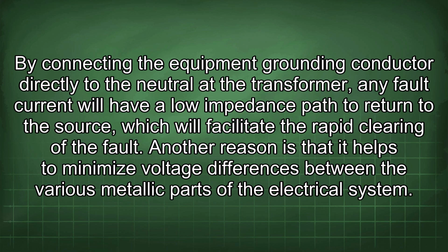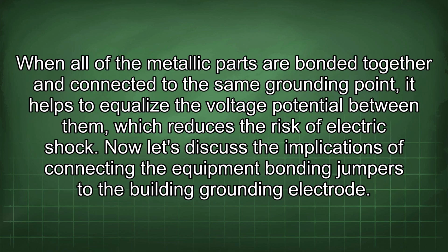Another reason is that it helps to minimize voltage differences between the various metallic parts of the electrical system. When all of the metallic parts are bonded together and connected to the same grounding point, it helps to equalize the voltage potential between them, which reduces the risk of electric shock. Now let's discuss the implications of connecting the equipment bonding jumpers to the building grounding electrode.